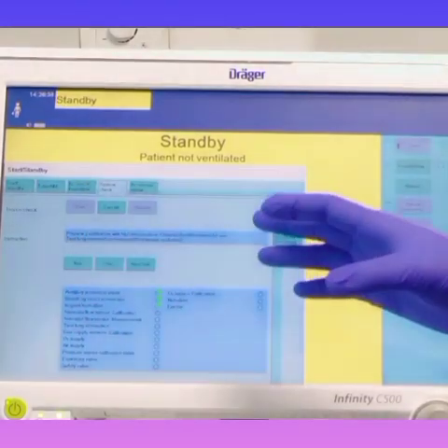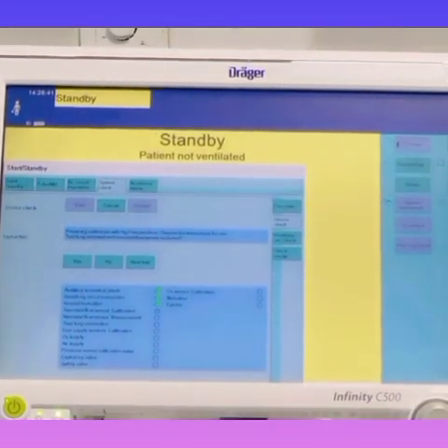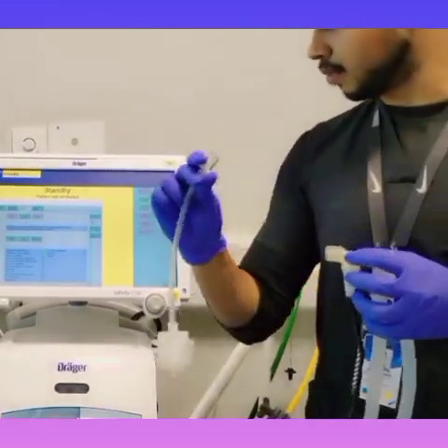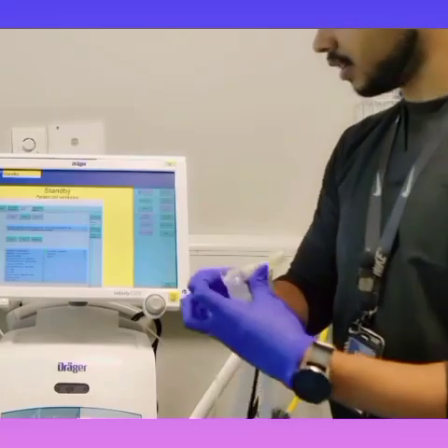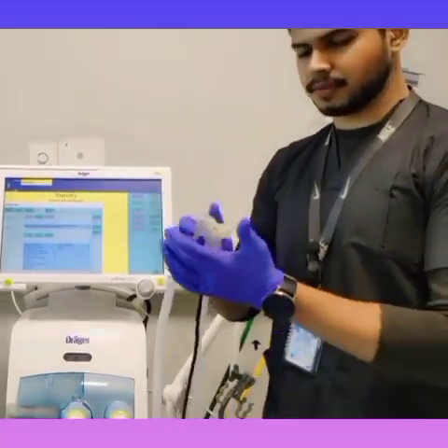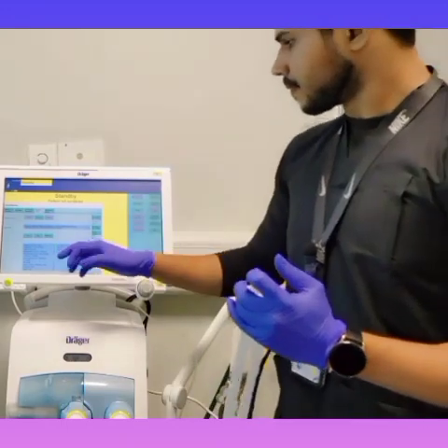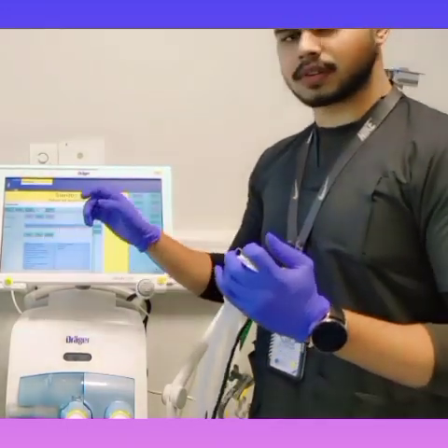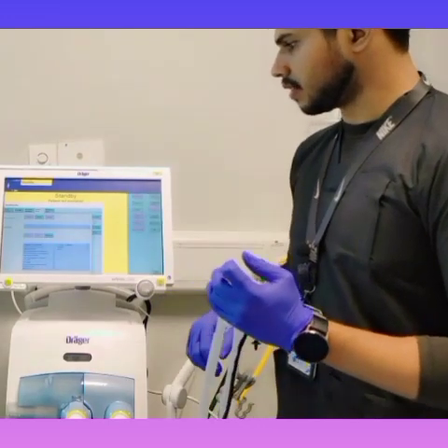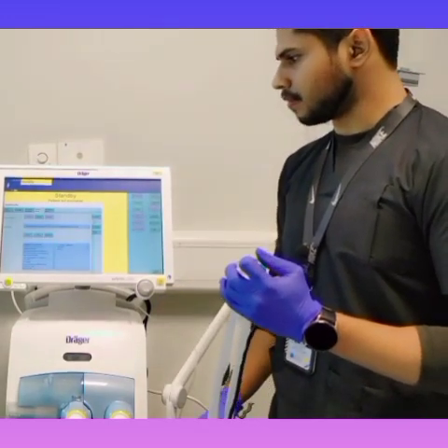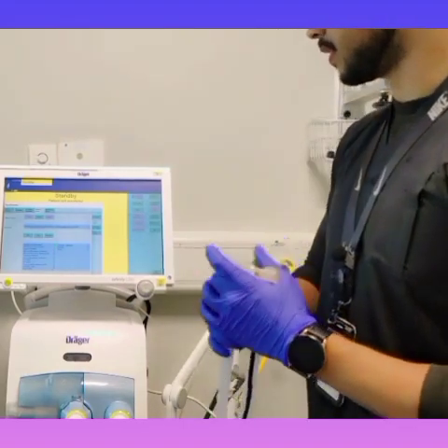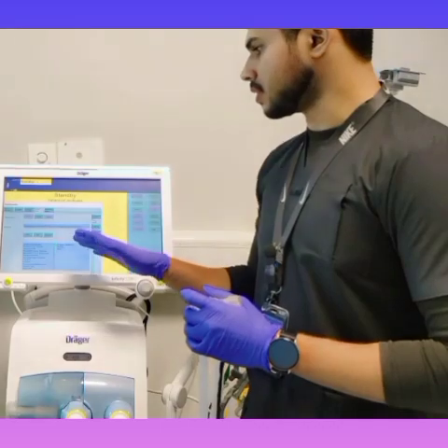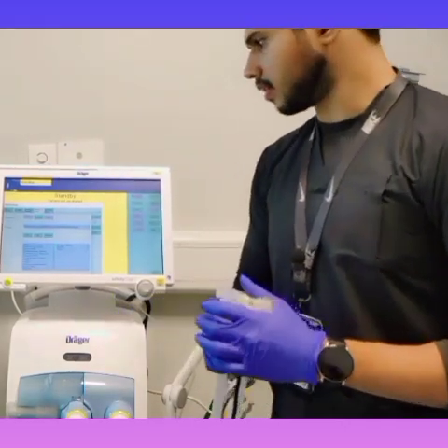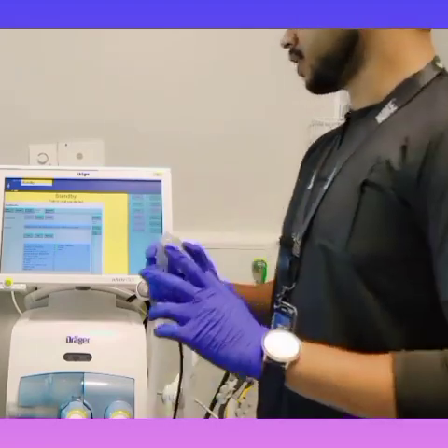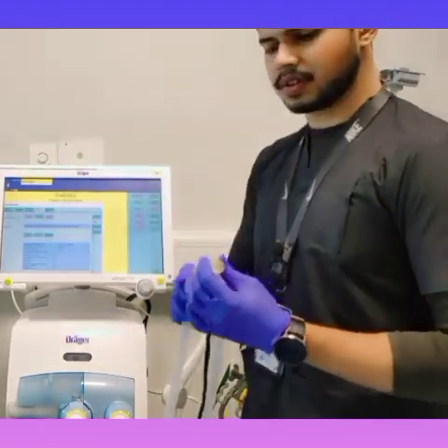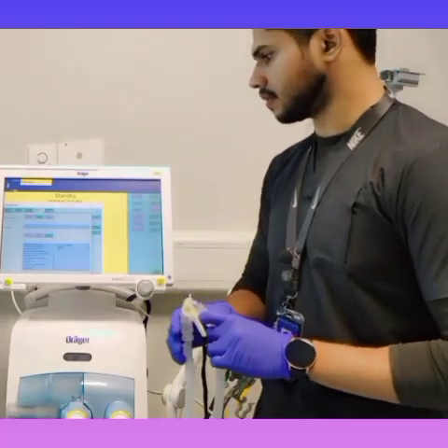Test lung removed and neonatal flow sensor occluded. So here we have the test lung removed, and neonatal flow sensor occluded. You have to occlude the flow sensor from the front side. Now, after occluding the flow sensor, you have to press yes. Wait for a minute. Okay, it's calibrated now. Test lung removed, neonatal flow sensor correctly installed and not occluded. It is not occluded. Yes.